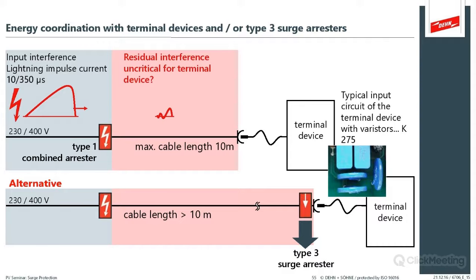And on this topic as well, for interest, we've done tests with some of the inverters, like the Huawei inverters, the 185 KTL inverter specifically, to specifically prove coordination with the internal type 2 surge arrestors and the larger type 1 surge arrestors on the outside, which they did pass.